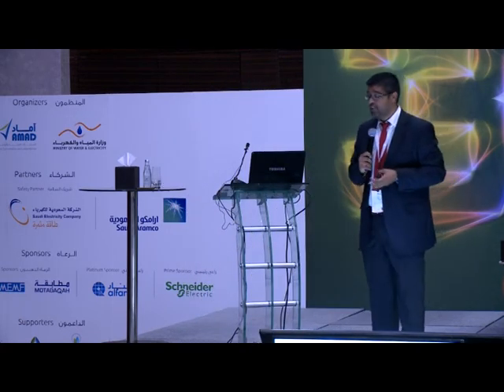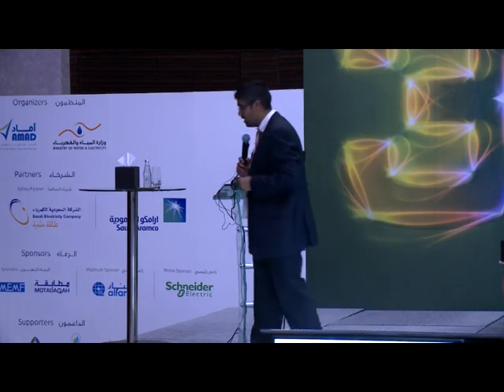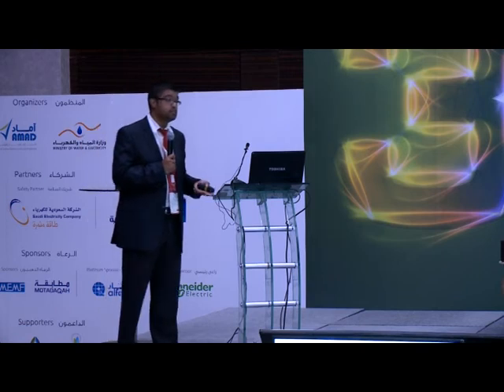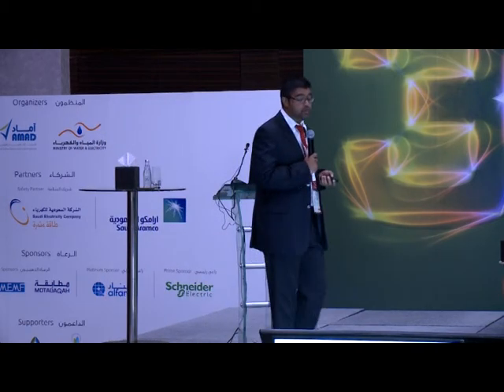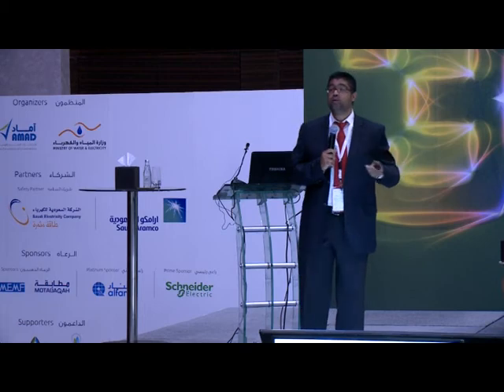The greater hazard concept refers to a situation where, for example, you've got a hazardous classified area, a hazardous location, and you need to switch off the main ventilation fans. If you do that, or if it's a life support system, you could end up creating a greater hazard.